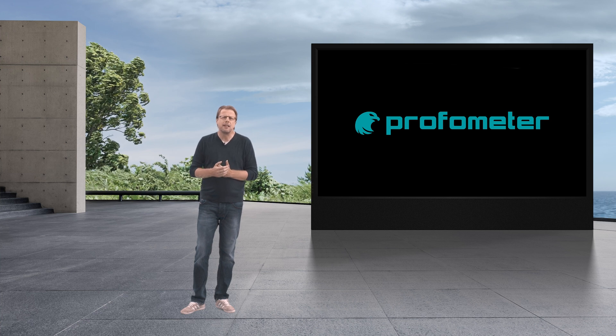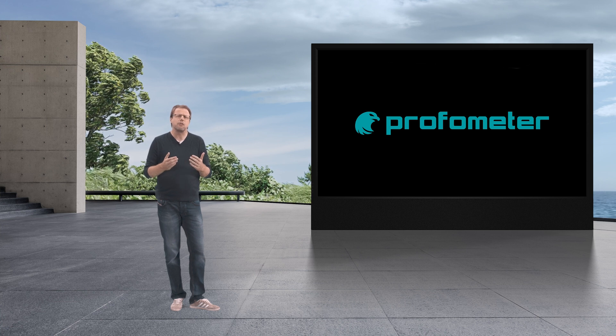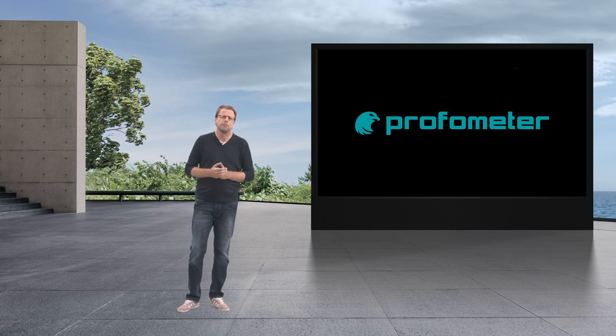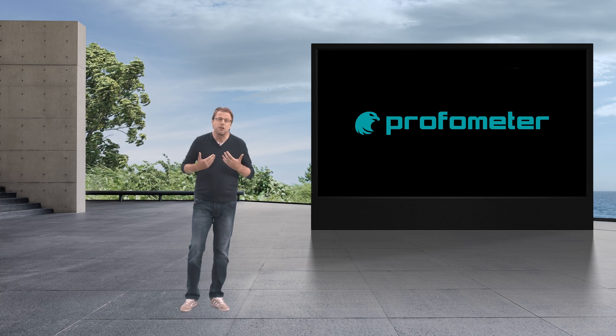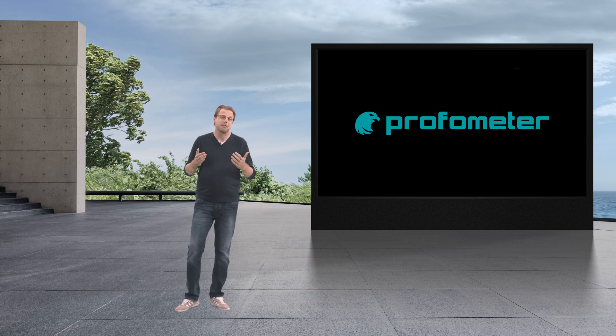Eddy Current is independent of the concrete properties and a very targeted technology for detecting rebars in the first 18 cm. We originally invented Profometer back in 1973. Over the past years, our team went back to the drawing board, consolidated those decades of experience and customer feedback to develop the Profometer that we always wanted to develop, but have only been able to do so now, thanks to the tremendous advancement in data processing possibilities.